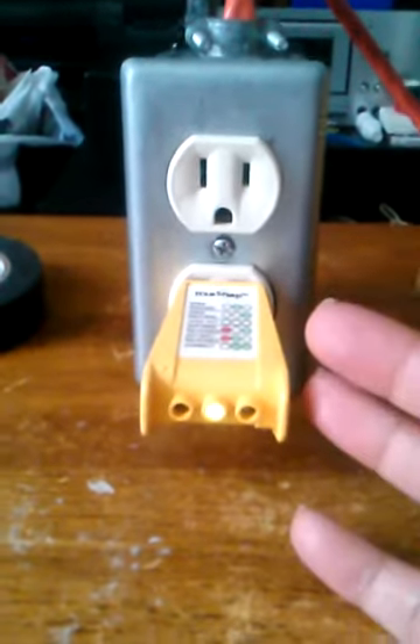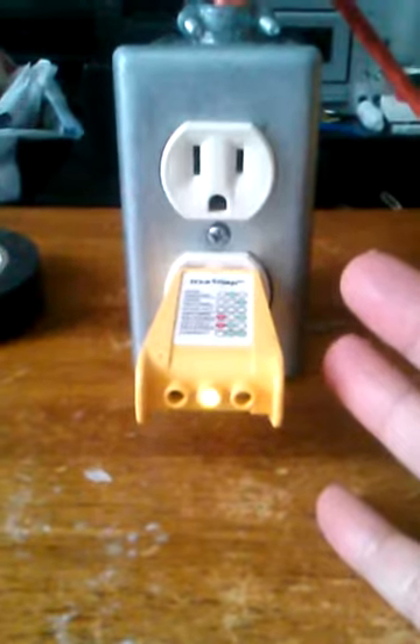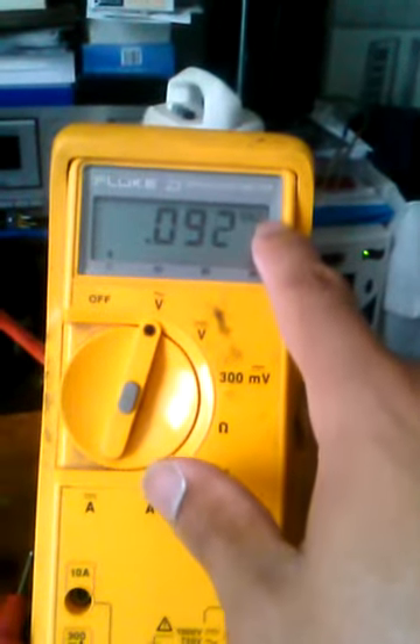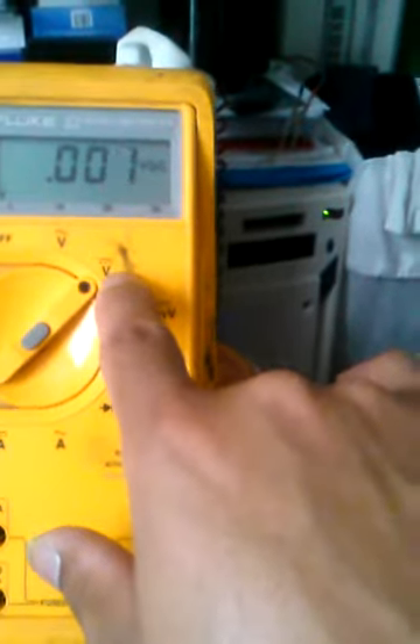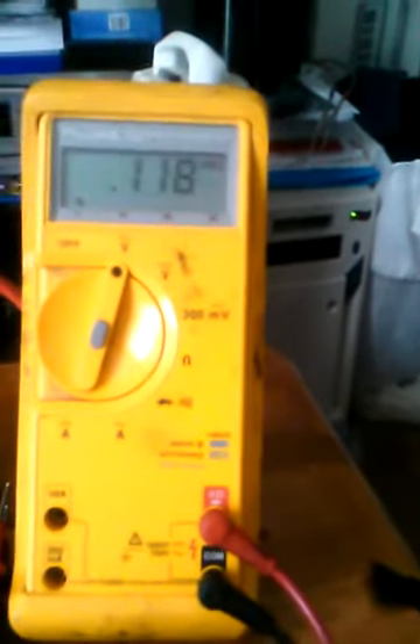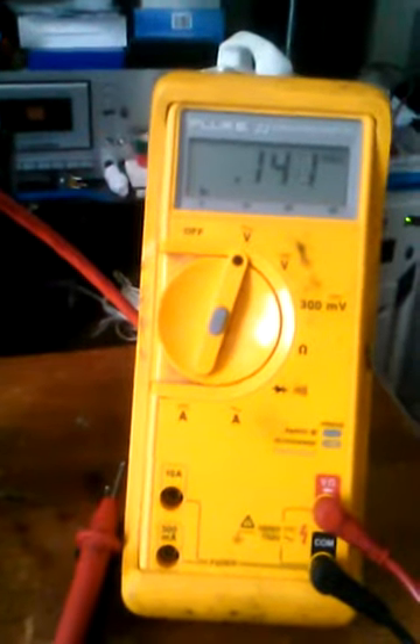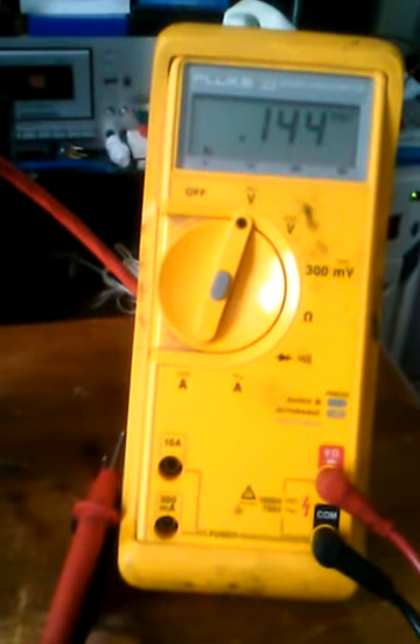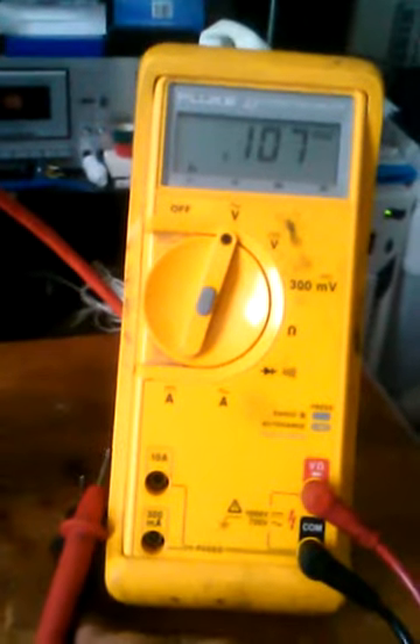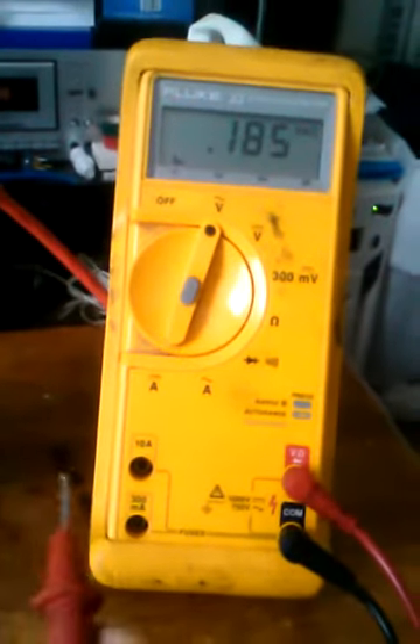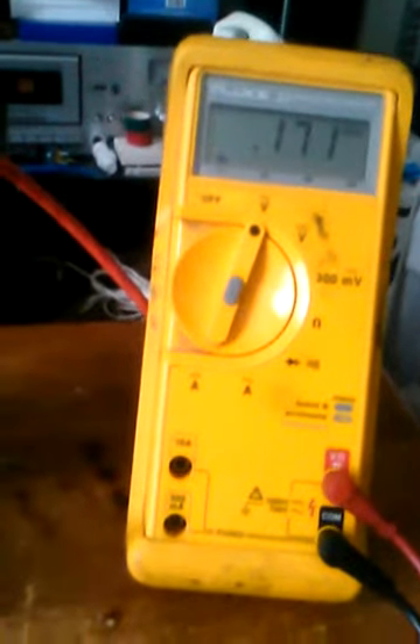And to test for an open ground with the multimeter, let's just say if you don't happen to have this handy electrical outlet tester, you can use, again, the same multimeter. You set it to AC. It should say so on the multimeter, volt AC. The next switch is for DC, but since we're working on AC circuits now, which is the power that's coming from the electrical panel to the wall receptacle in your house or condo or place of business or an apartment, that's always going to be set to AC, and it should be at 120 volts maximum.